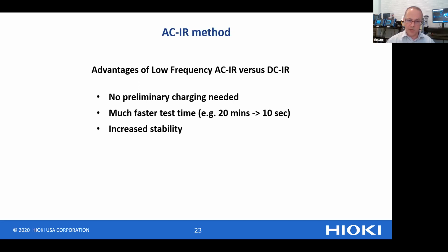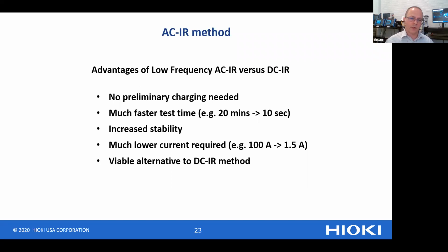Also increased stability and repeatability of the results. And much lower current is required. What would have taken 100 amps with the AC-IR low frequency may only take 1.5 amps. And so this is a viable alternative to the DC-IR method.